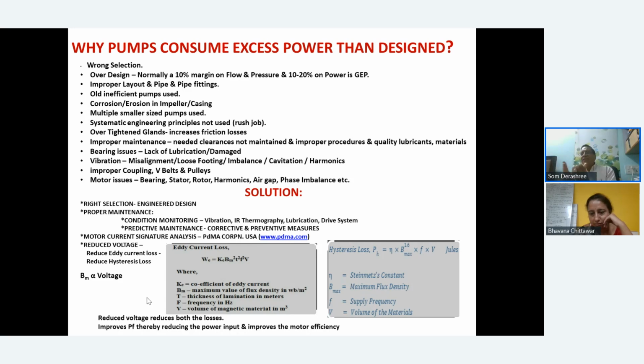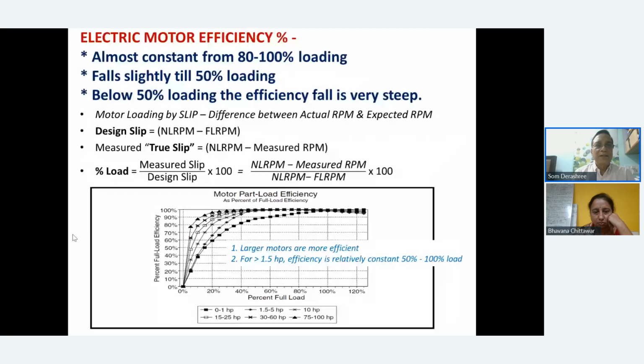So let's say we always suggest that around 400 volts, if you run, that's fine. Of course, it is done through transformer tap changing. That is the only mechanism available to you. So when you do a transformer tap change, make sure that the farthest point from the transformer is not hungry for higher voltages. Let's say you have a high torque requirement somewhere, because torque also is proportional to the voltage. So if there is a torque application or a conveyor application, it should be either fed through a separate route or maybe stepped up, because the rest of the motors can have an impact on the eddy current and hysteresis losses. And for this particular application, you can have a voltage booster or stabilizer put in to improve the voltage so that it does not hamper the operation. So you have to trade off basically and see what is the optimum value. Motor, as you say, almost constant.